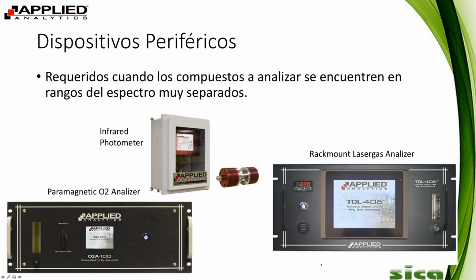And here you can see what the rackmounts look like. Here is a TDL, which we use for low ammonia measurements, low ppm ammonia measurements. We would typically measure ammonia with the OMA for percent level or high ppm. But we had a lot of customers coming to us with low ppm ammonia applications, so we developed the TDL, and that's what we use for that.